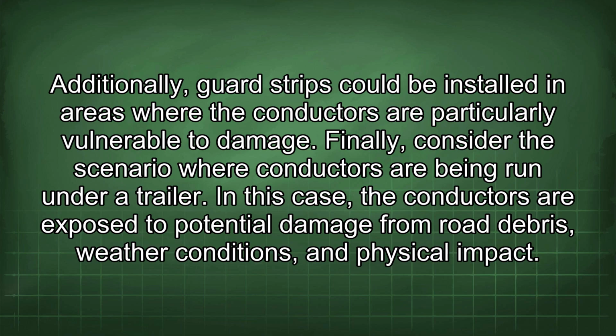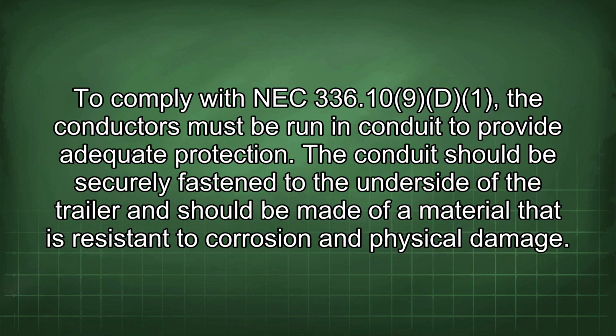Finally, consider the scenario where conductors are being run under a trailer. In this case, the conductors are exposed to potential damage from road debris, weather conditions, and physical impact. To comply with NEC 336.10, the conductors must be run in conduit to provide adequate protection. The conduit should be securely fastened to the underside of the trailer and should be made of a material that is resistant to corrosion and physical damage.